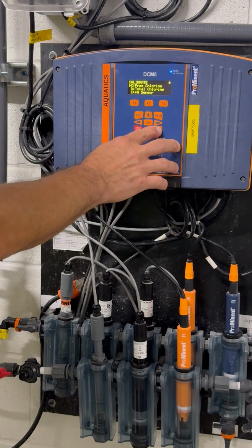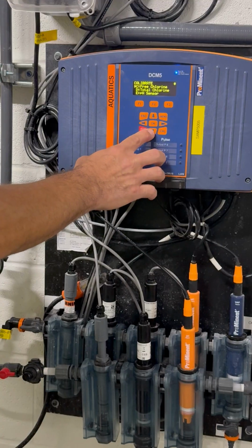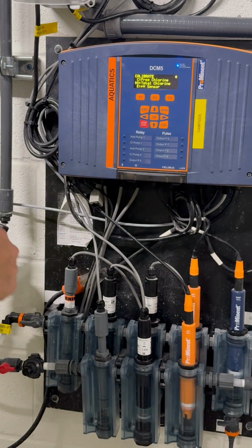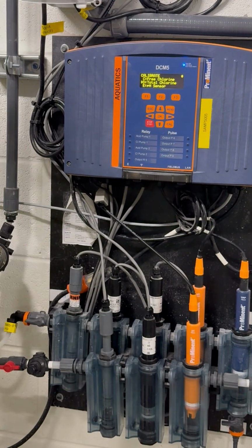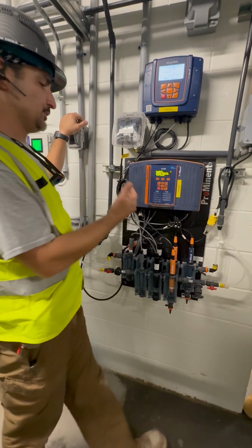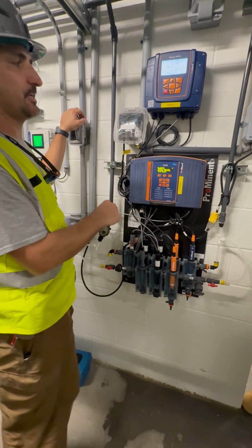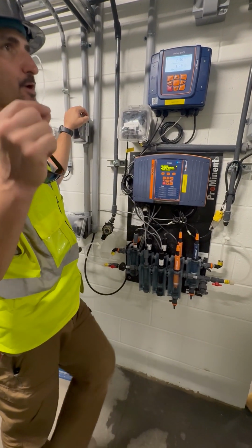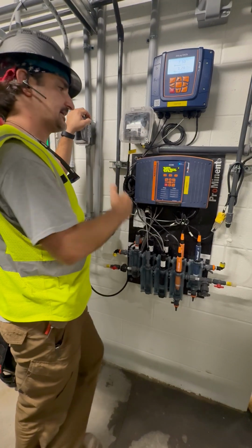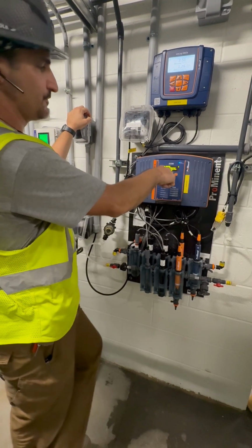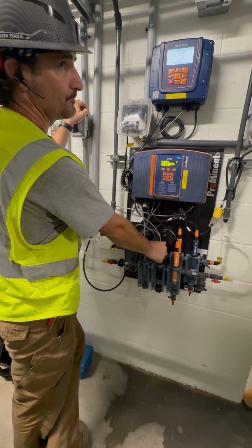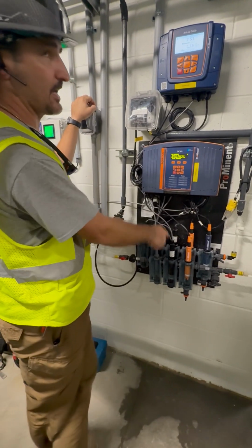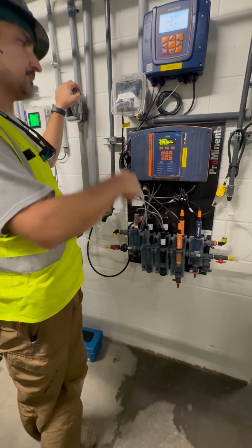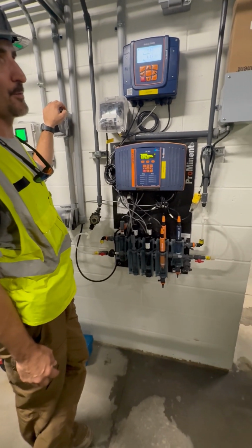You can also calibrate your free chlorine and total chlorine. As your sensors start getting out of whack, or you're losing your gel or electrolyte in your sensor, you can start to calibrate farther and farther out, and then it'll bring you back to 0 again. When you factory reset, you're going to re-gel or put new electrolyte in your sensor, in your probes, and then you'll bring it back down to 0 again with a factory reset.